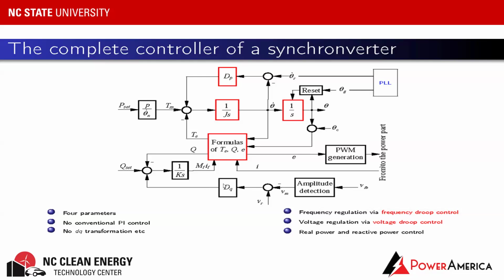There are in total 4 control parameters: DP and DQ, and J and K. DP and DQ are basically the droop control coefficients. These are determined when you sign a contract with the utility. They will tell you, maybe we want the frequency droop to be 0.5% droop for 100% change of the real power. And for the voltage, we normally allow 5% droop for 100% change of reactive power.